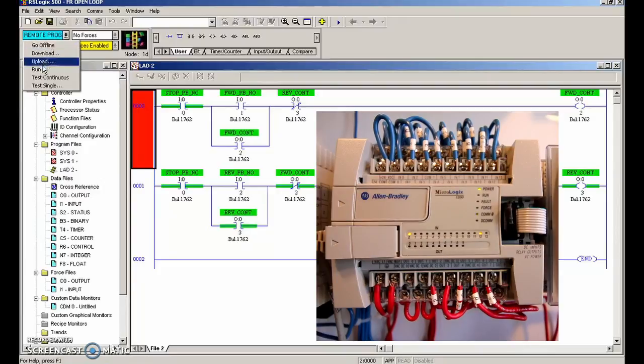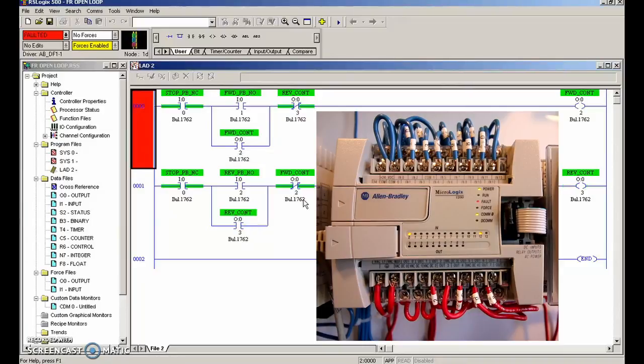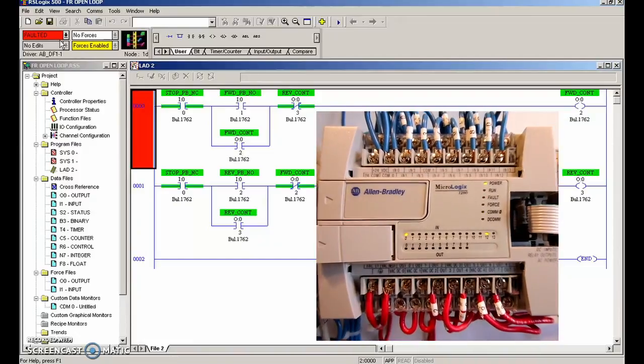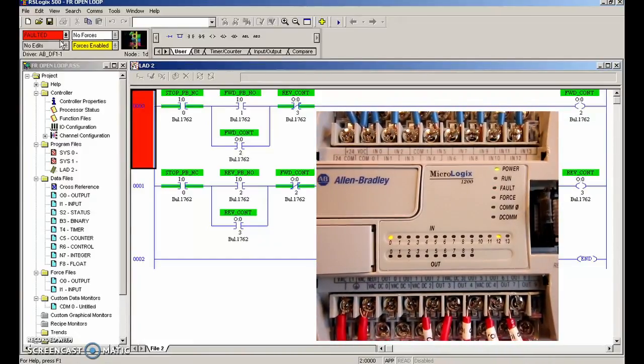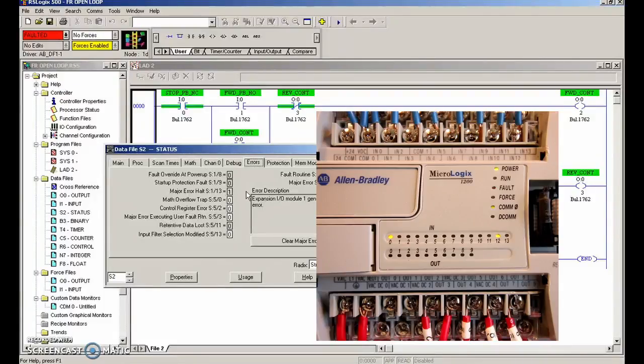As soon as we go online, oh look at this — it put me into remote program. Let's put it into run mode now. As soon as we do that, two things happen: this is screaming that we have a fault, and you can see the fault LED screaming at us on the PLC. So we need to get rid of that. What caused that fault? Let's go to the error and see — it says the expansion IO module 1 generated an error.